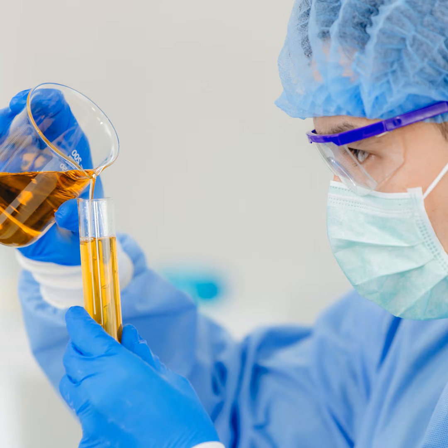One of the traditional methods is microscopic analysis. The concept is surprisingly straightforward. A measured sample of oil is passed through an extremely fine membrane. That membrane acts like a filter, trapping the contaminants while allowing the clean fluid to pass through. Once the sample has been filtered, the membrane is placed under a microscope for examination.